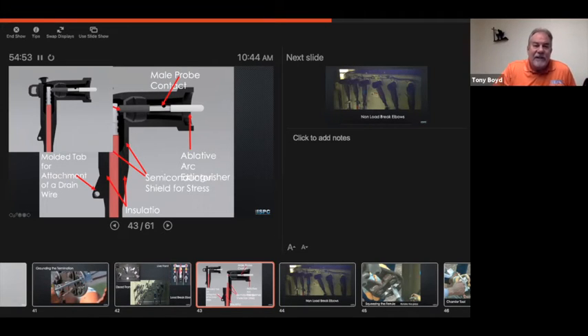All right, we have the semiconductor. You notice that at the end of the semiconductor shield down here, it begins to expand. And again, that takes those stress lines and makes them go outward and evenly. Here at the end of the insulation, where the conductor connector is, then we have some airspace, very important in that airspace to allow all of the current leakage to go out. And then down here is an eye. A lot of folks call this a grounding eye, and it is not a ground eye. It will not ground the elbow.